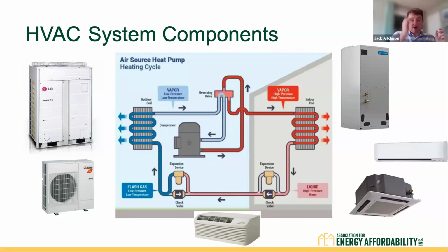On the left are your heat pumps. Those are your outdoor units. That is going to contain your compressor, your outdoor coil, your expansion device, really everything on the left of that diagram in the middle. And then on the right are your indoor components. That's going to be your indoor coil. And then on the bottom, you have your packaged heat pumps. These are heat pumps where it's located inside the unit. It's on an exterior wall, and all of the heat pump components are located in that one package unit.